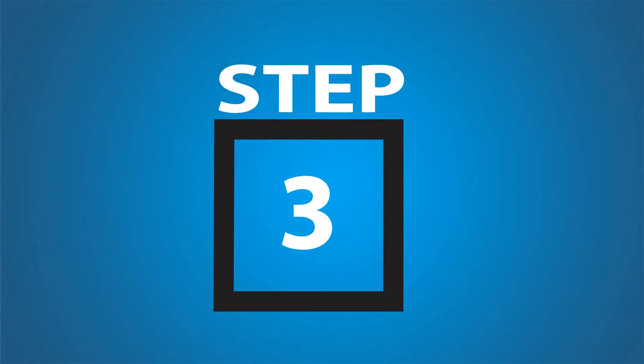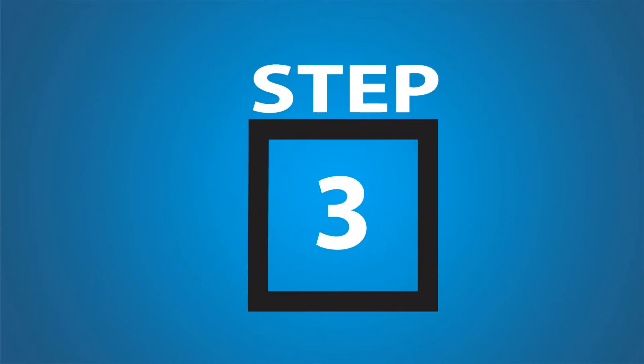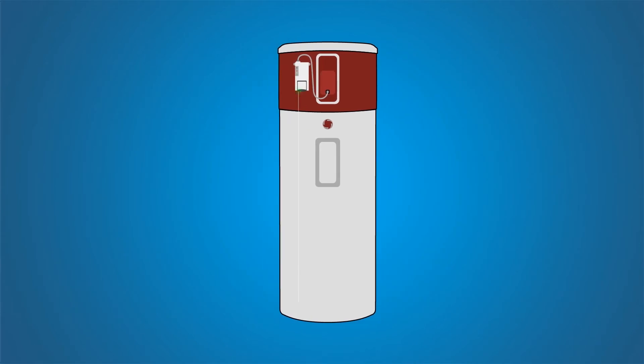Look for the small green light on the communication module. If the module is receiving a strong FM radio signal, it will blink several times a second. If you observe the yellow light blinking in a repeating pattern, please contact your utility for support.